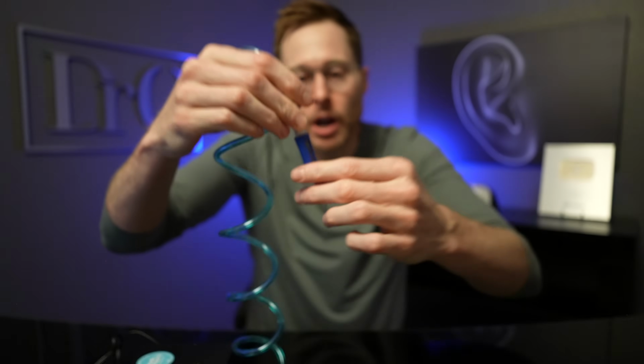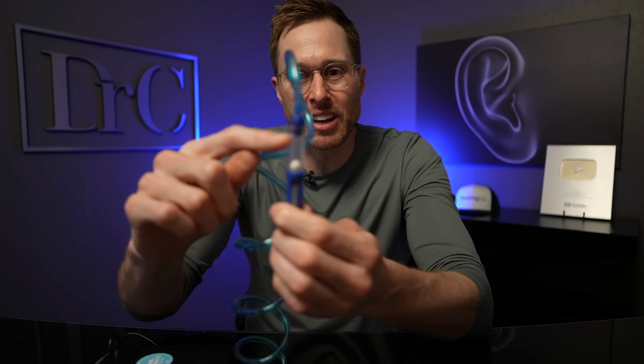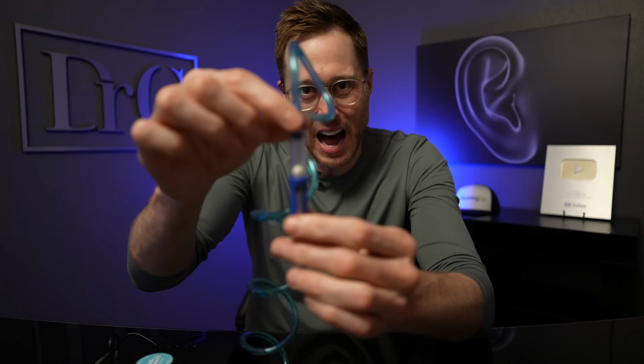Now, like I mentioned a little bit earlier, as you suction more and more debris from your devices, it will get trapped into the bottom part of the filter chamber here, to the point where even when you turn on the suction, that ball is not going to be sucked up to the top of the chamber on the top part here, which means that you need to replace the filter at that point.